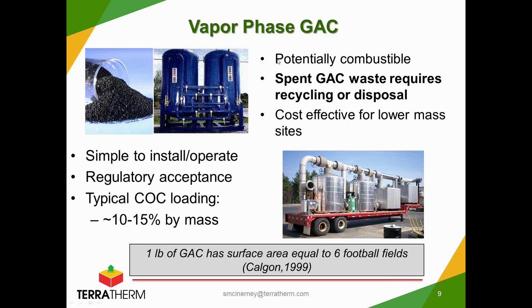I'm not going to get into all of the design details around it, but just recognizing that certain contaminants have a heat of adsorption that could cause some problems with carbon in terms of the risk of bed fire and other operating conditions like that. So they're not foolproof systems, and anytime you've got the right mix of contaminants and the right operating conditions, you need to make sure that the systems have built into them some safeguards to detect temperature rise in the beds and be able to isolate these systems and prevent a breakout of a bed fire.